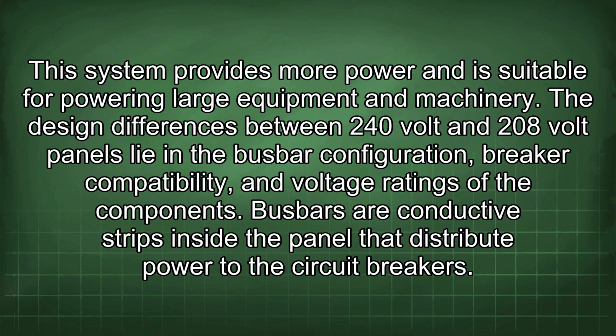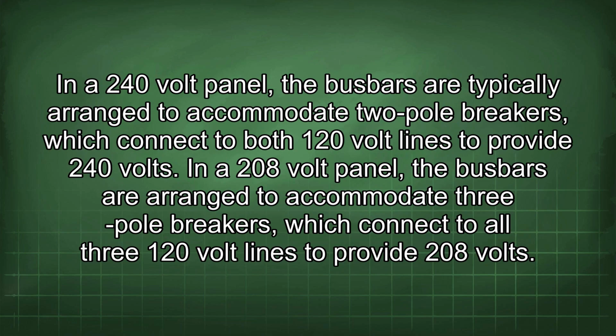The design differences between 240-volt and 208-volt panels lie in the busbar configuration, breaker compatibility, and voltage ratings of the components. Busbars are conductive strips inside the panel that distribute power to the circuit breakers. In a 240-volt panel, the busbars are typically arranged to accommodate two-pole breakers, which connect to both 120-volt lines to provide 240 volts. In a 208-volt panel, the busbars are arranged to accommodate three-pole breakers, which connect to all three 120-volt lines to provide 208 volts.